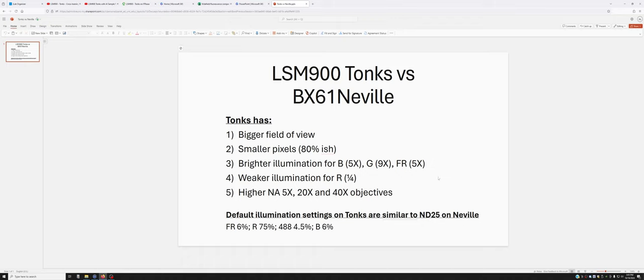It has brighter illumination for the blue, green, and far red channels by 5x, 9x, and 5x respectively. That means you could go five times brighter than the brightest you can go on the BX61 for the far red, for example. It has weaker illumination for the red channel—only about one-fourth of the power of the red illumination on Neville.